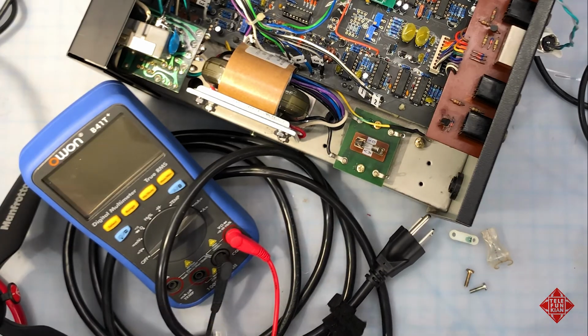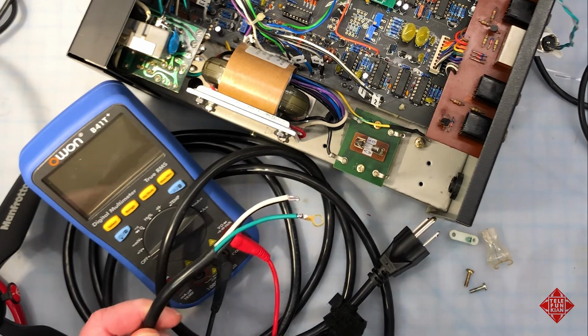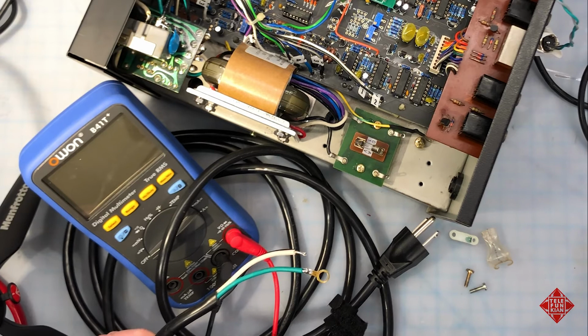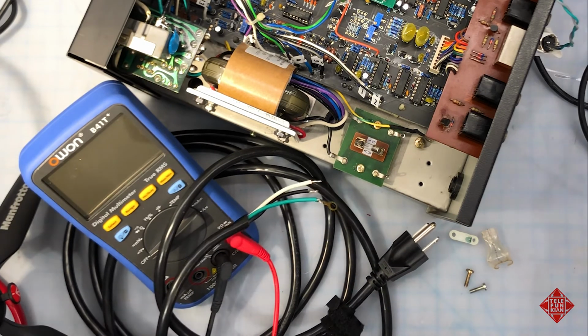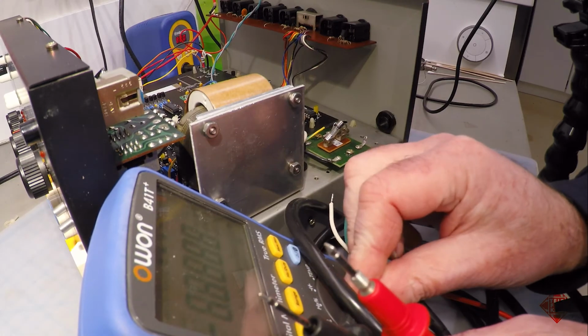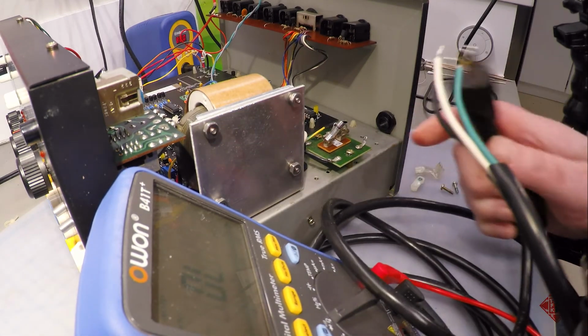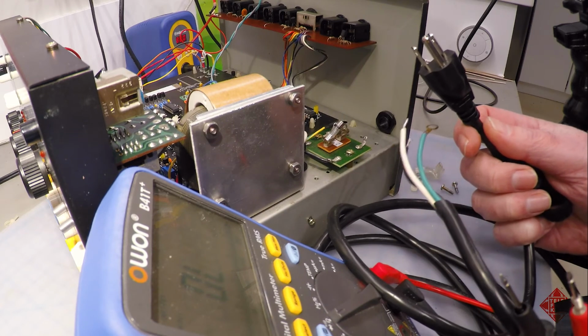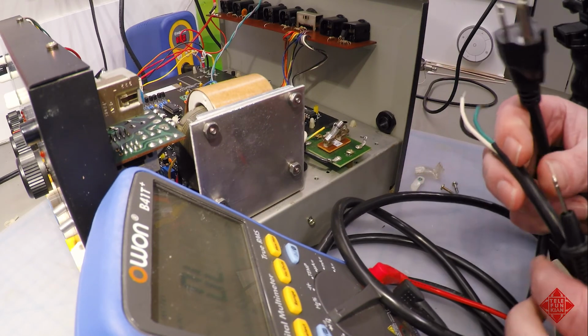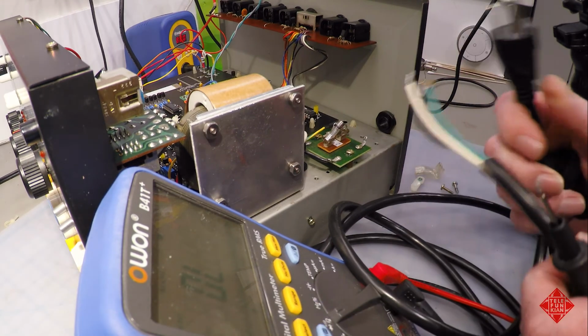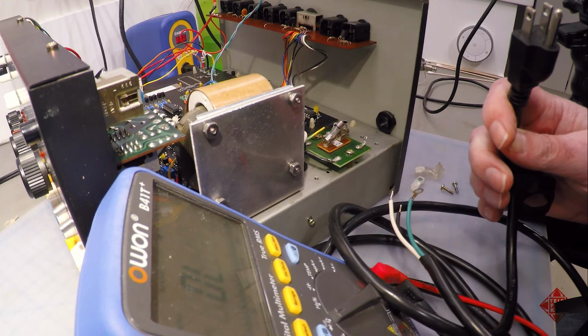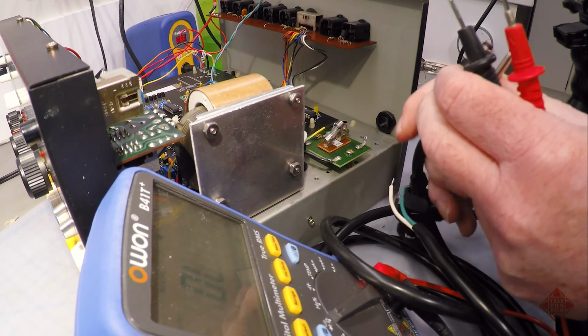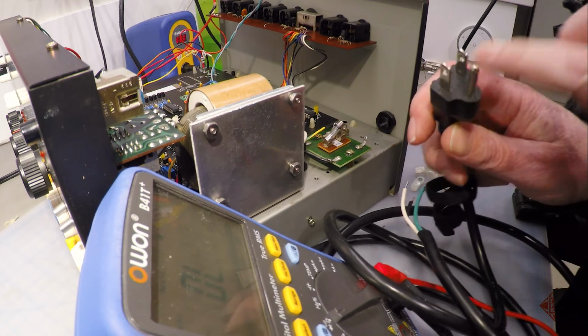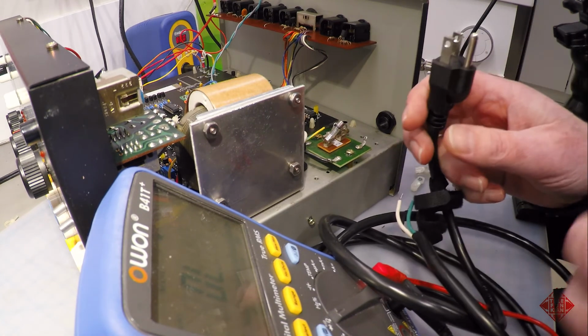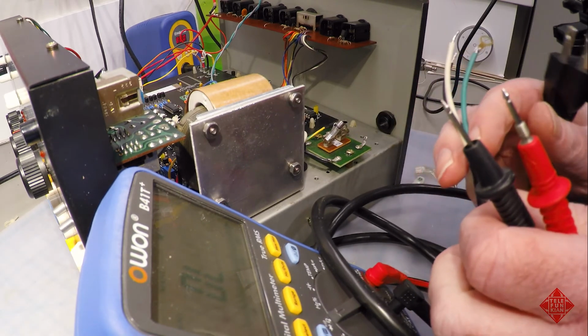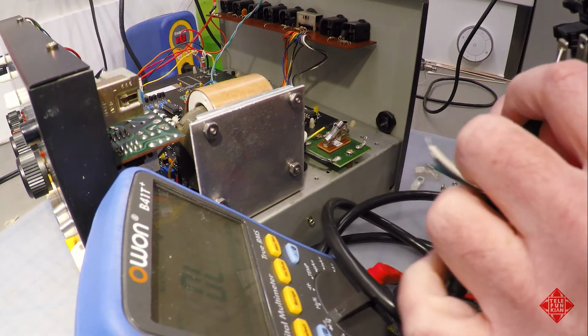When replacing the AC power cable on the CR-78 or any other instrument for that matter, we don't take anything for granted because safety is at stake. And in particular, there are many examples where you can find power cables available for sale, usually online, and oftentimes these will have the leads wired incorrectly. On this particular cable, we have the live and the neutral labeled on the plug, and what we're hoping is that the live and the neutral are connected to the appropriately colored wires.